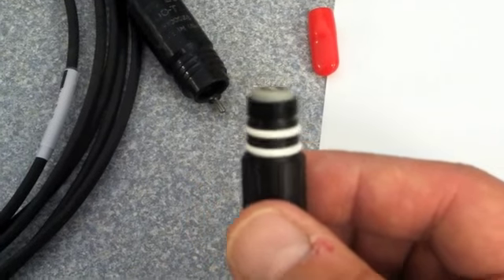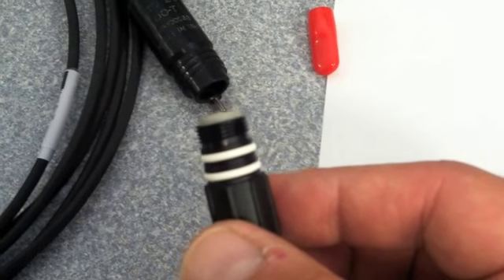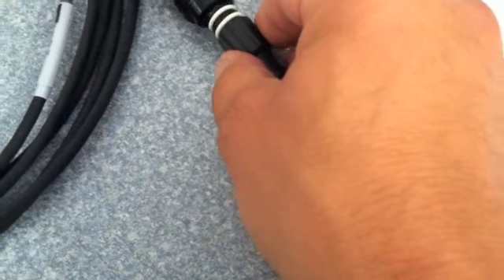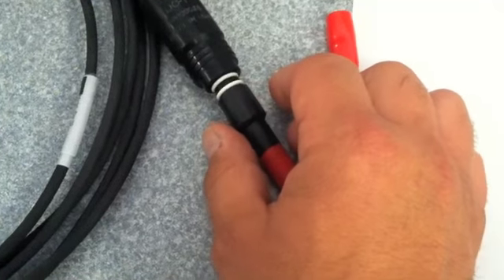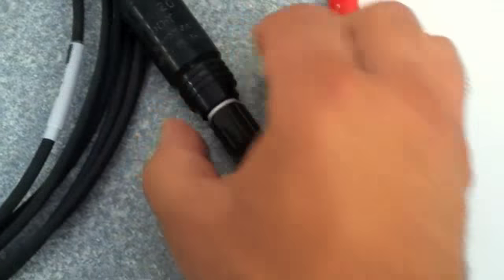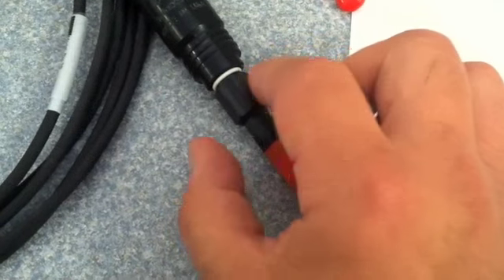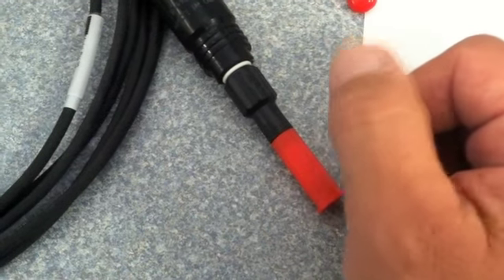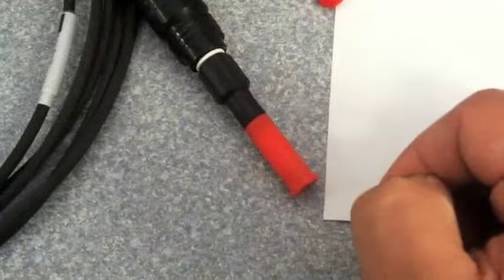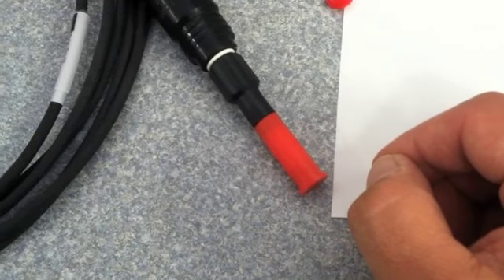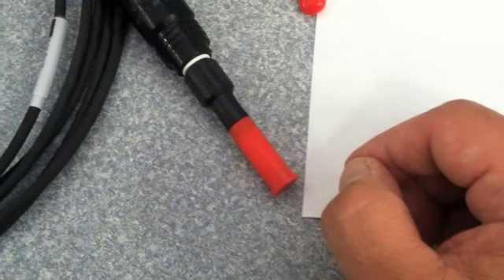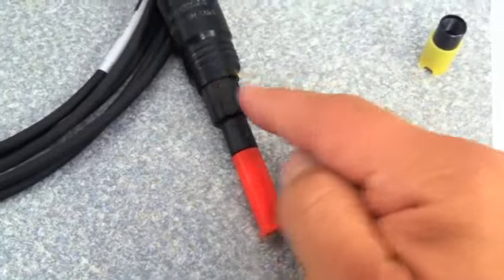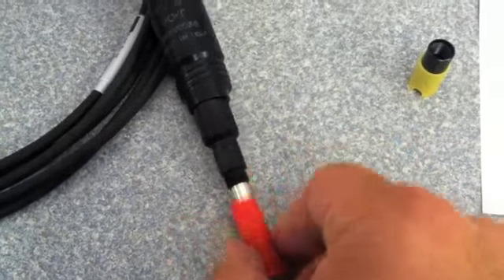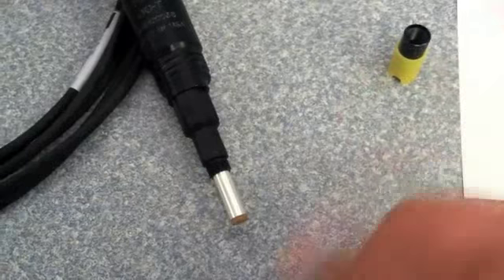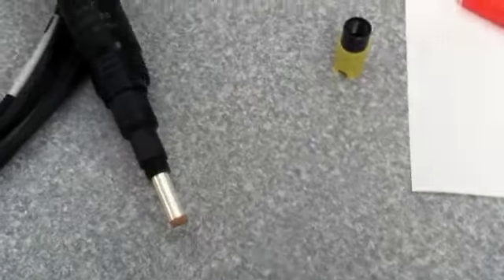When you take the O-ring out of the box, there's going to be a little bit of O-ring grease already on, and we're just going to insert it into the probe, and then you're going to push it so the first O-ring is seated before we continue to turn the module up into the cable assembly, and just get it finger tight. You don't want to over tighten it, but you do want it to seat and have those O-rings to protect the cable. Once you have the sensor finger tightened, we can now prepare the cap and the solution and to complete the install.